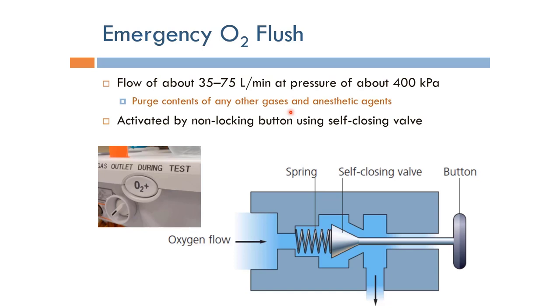This is activated by a non-locking button, which looks like this, and the actual diagram of it looks like this. Basically, this is a self-closing valve. When we are not pressing this button, the self-closing valve closes the opening and allows no oxygen to flow. Whenever we push this button, the oxygen has a path to flow from outside to the breathing circuit.